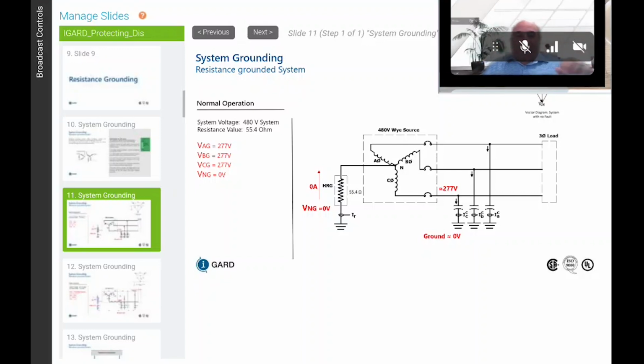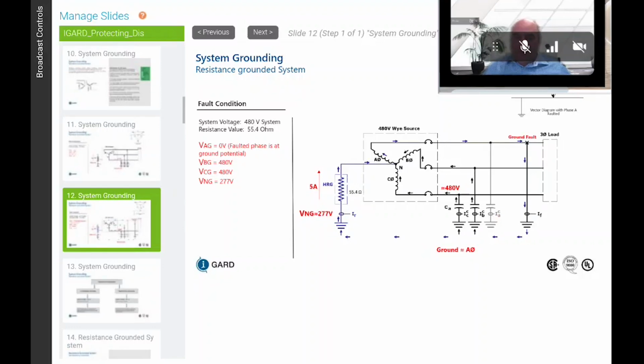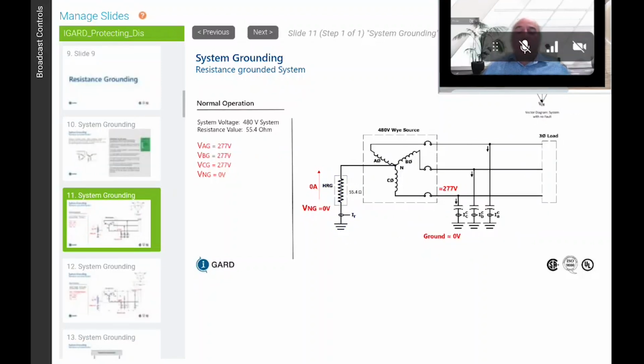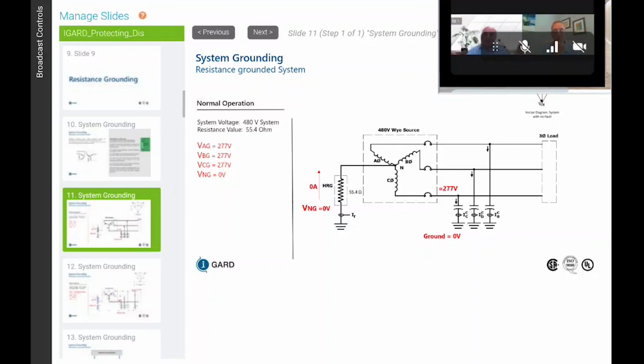I apologize for that. I think you're looking at this slide here, and when there is no fault on the system, you're going to have charging current. Charging current is basically the amount of current flowing through the capacitor to ground. All your conductors in your facility act like capacitors.